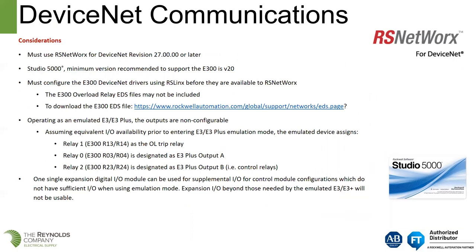Considerations for the DeviceNet adapter: you must use RSNetWorx for DeviceNet version 27 or later. For Studio 5000, the minimum version is 20. You must configure the DeviceNet drivers using RSLinx before they're available in RSNetWorx. There's a link we can provide for downloading EDS files. When operating an E300 in emulated E3 Plus mode, the outputs are non-configurable, and the I/O will match what you had on the E3 Plus.